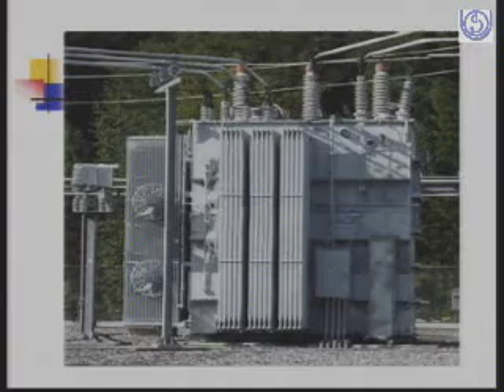So what are the losses in a transformer? This is the most important part for a distribution transformer. The losses are of two types, the load losses and the no load losses. The load losses are proportional to the square of the load current. So these depend on the loading of the transformer.